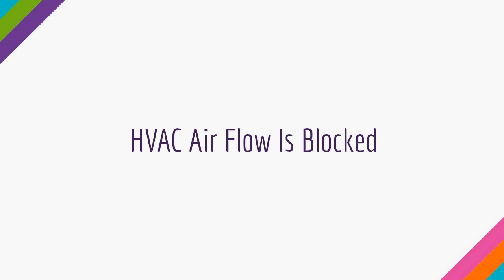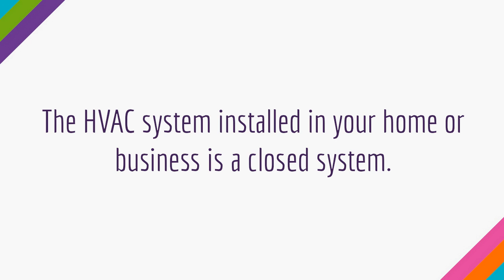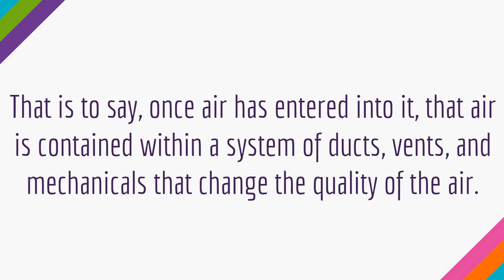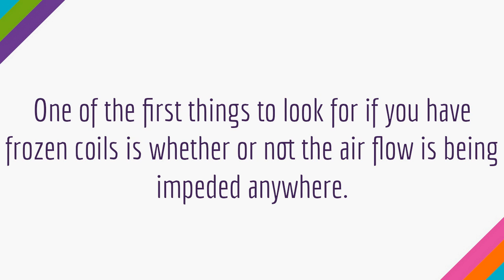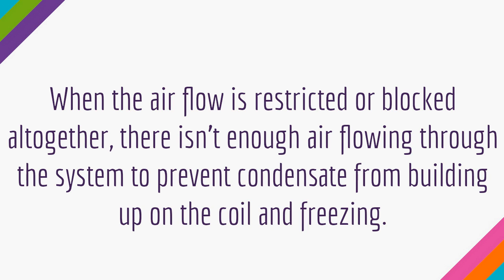HVAC airflow is blocked. The HVAC system installed in your home or business is a closed system. That is to say, once air has entered into it, that air is contained within a system of ducts, vents, and mechanicals that change the quality of the air. One of the first things to look for if you have frozen coils is whether or not the airflow is being impeded anywhere. When the airflow is restricted or blocked altogether, there isn't enough air flowing through the system to prevent condensate from building up on the coil and freezing.